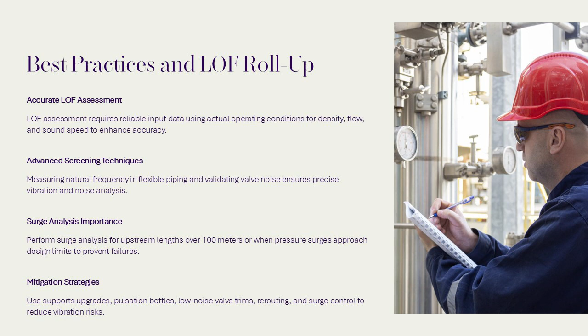After calculating LOF for all applicable mechanisms, the governing LOF determines prioritization for mitigation. Common corrective actions include upgrading supports, installing pulsation bottles, using low-noise valve trims, rerouting dead legs, implementing surge control systems, and adjusting anti-stall controls. This integrated approach ensures that high-risk areas are addressed effectively, reducing the likelihood of vibration-induced fatigue failures and improving overall plant reliability.